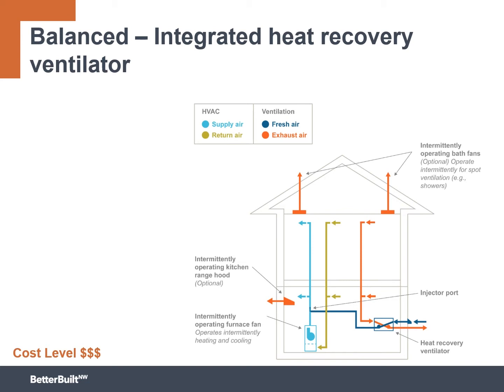However, it also means that we may be relying on the air handler fan to move the air around, which is a lot higher energy draw than just using the fans included in the heat recovery ventilator. This integration will likely work best when connected to the supply side of your central distribution system, which may sound counterintuitive. We'll go into that more later. And we do this with an injection method connecting the ducts, not just with a saddle tee or a takeoff. Connecting to the return side can be done, but may require things like constant airflow regulators, different strategies for where you put your filters, and maybe even larger size return ducts. And this might be necessary to prevent hyperventilating your heat recovery ventilator. As you can see, there also can be some nuanced ductwork that needs to happen with this type of integration.